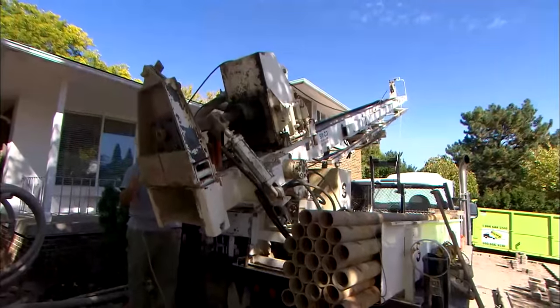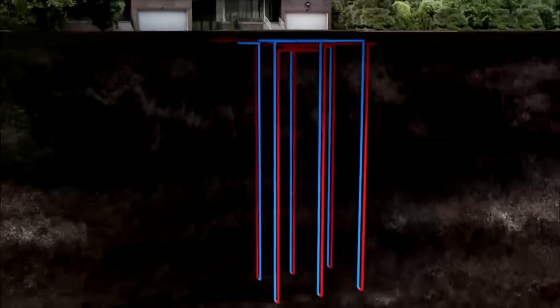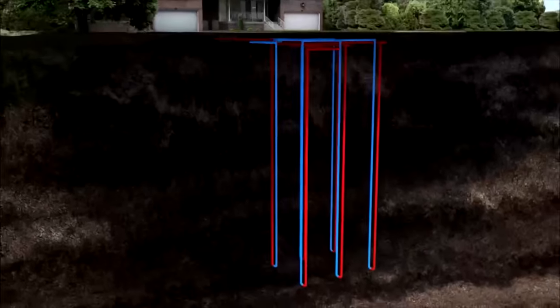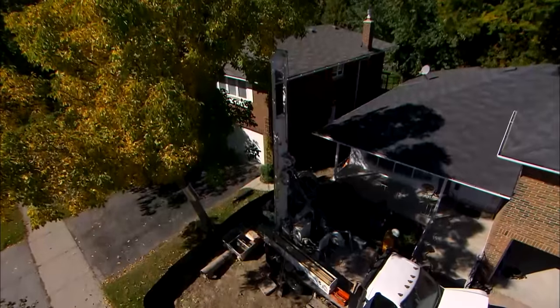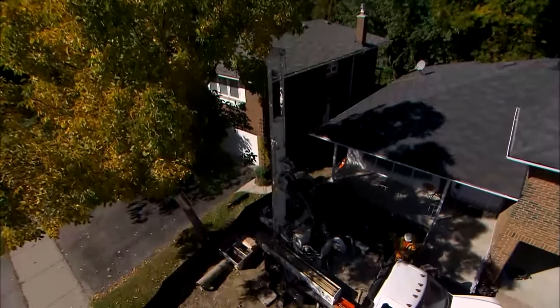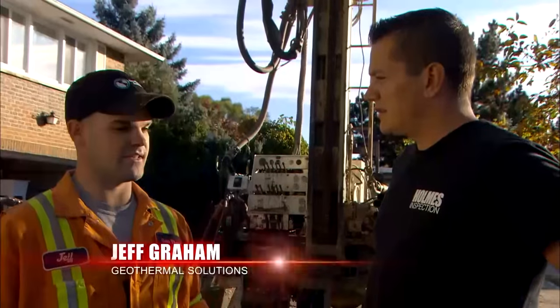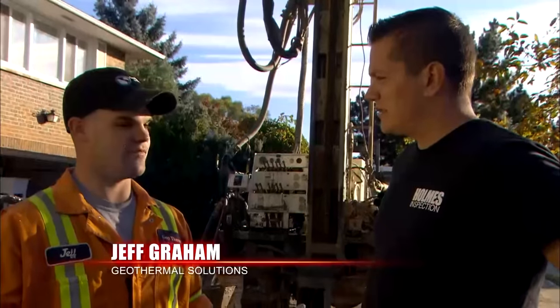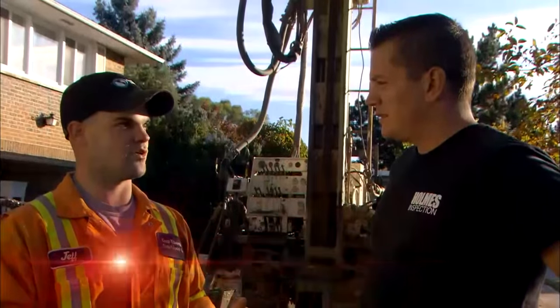Drilling geothermal heating, we've got 6 holes to do at 135 feet. We're expecting mostly sand and clay here, so it should be pretty easy drilling. We stick 10 feet apart always per hole, just to get the heat out of the ground properly. If they're too close together, the system's not going to work properly.